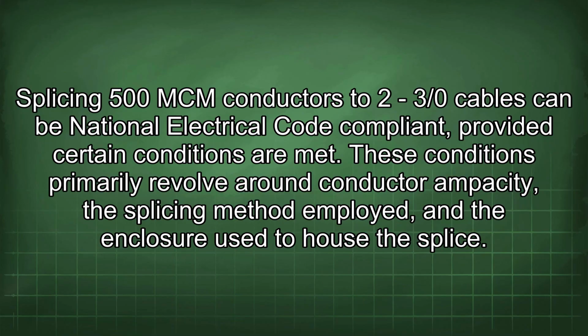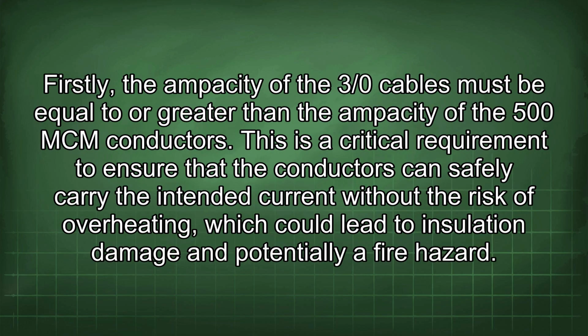Splicing 500 MCM conductors to 3/0 cables can be National Electrical Code compliant, provided certain conditions are met. These conditions primarily revolve around conductor ampacity, the splicing method employed, and the enclosure used to house the splice. Firstly, the ampacity of the 3/0 cables must be equal to or greater than the ampacity of the 500 MCM conductors. This is a critical requirement to ensure that the conductors can safely carry the intended current without the risk of overheating, which could lead to insulation damage and potentially a fire hazard.